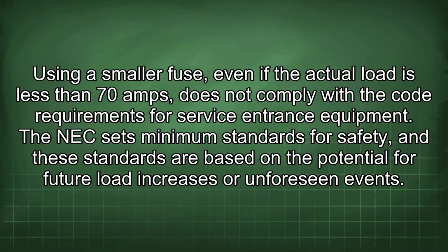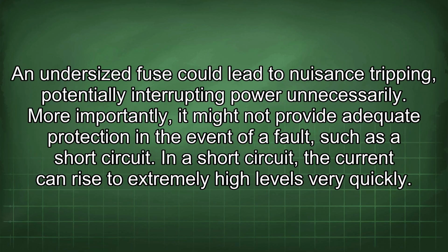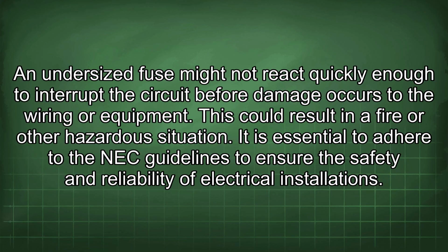The NEC sets minimum standards for safety, and these standards are based on the potential for future load increases or unforeseen events. An undersized fuse could lead to nuisance tripping, potentially interrupting power unnecessarily. More importantly, it might not provide adequate protection in the event of a fault, such as a short circuit. In a short circuit, the current can rise to extremely high levels very quickly. An undersized fuse might not react quickly enough to interrupt the circuit before damage occurs to the wiring or equipment. This could result in a fire or other hazardous situation.